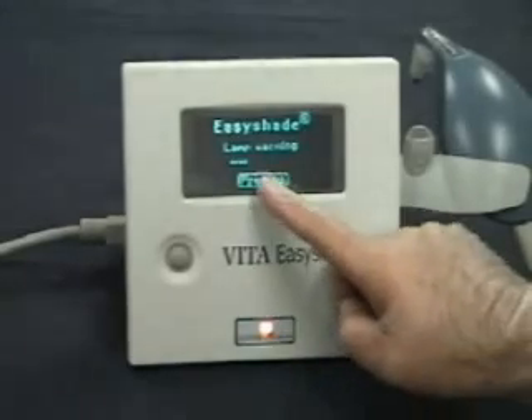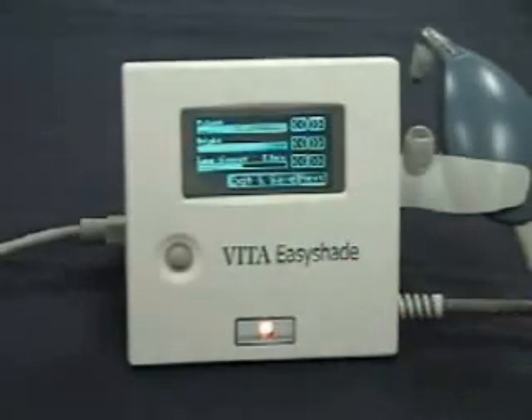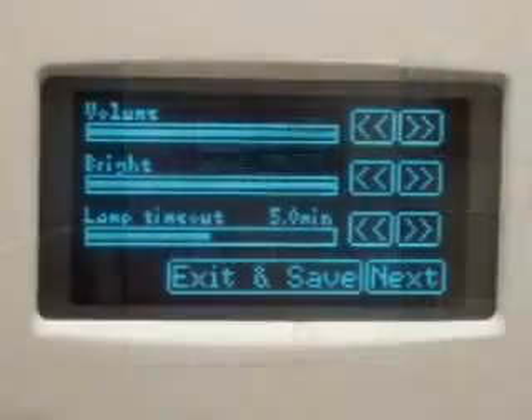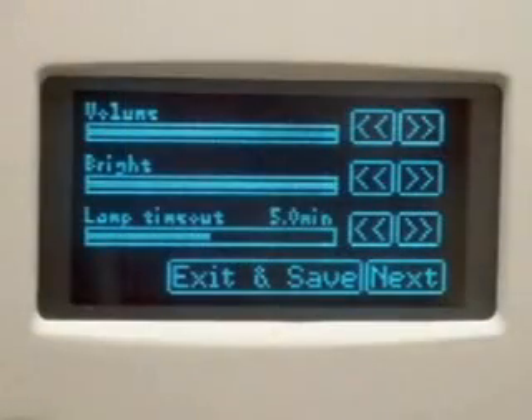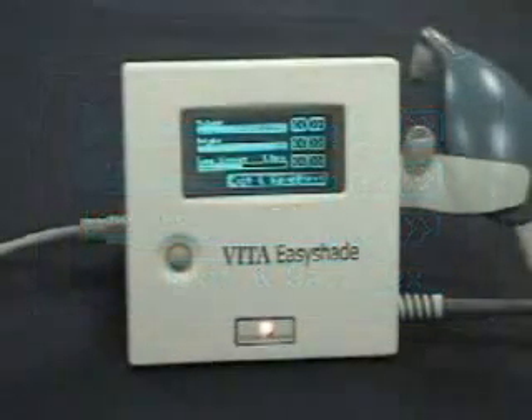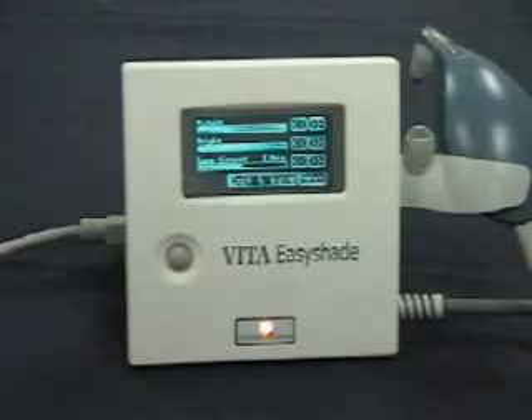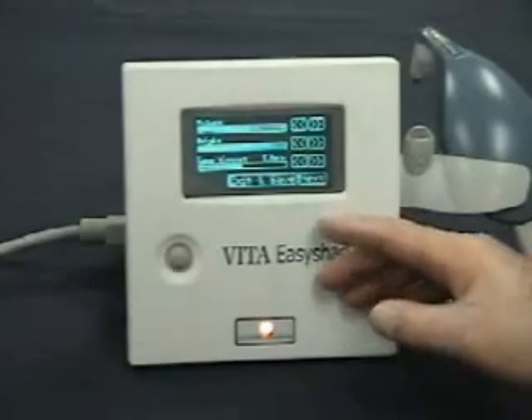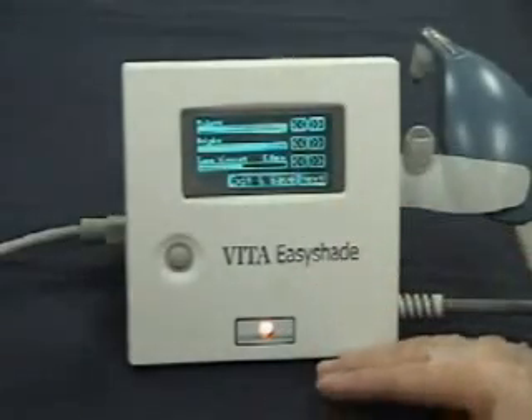By touching the Presets button, the display changes to the first page with adjustments of volume, brightness of the displays, and lamp timeout. This is the amount of time that the Easy Shade will wait before the device enters standby mode. It is not recommended to adjust the setting from its maximum of 10 minutes, as it can shorten the life of the internal light source. Adjustments are made via the arrows on the right of the screen. Should you wish to exit and return to the calibration and use of Easy Shade, simply press Exit and Save at any time. Assuming more preferences are required, press the Next button on the right of the display.